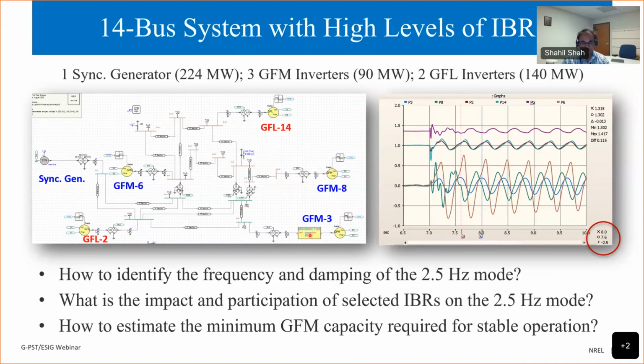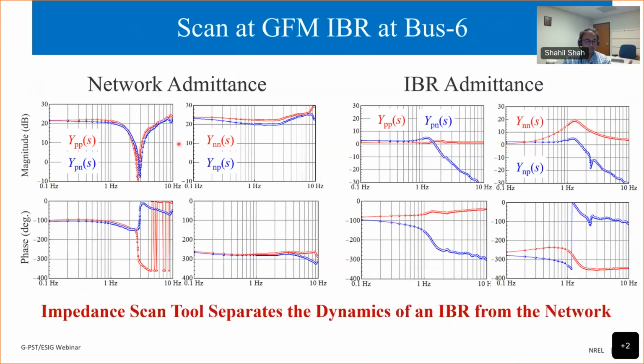Although here I am showing the block at the grid forming inverter at bus 3, first I'll show the impedance scans performed at the grid forming inverter at bus 6. Once we do that scan at this grid forming inverter at bus 6, this is what we get when we apply this tool. We see the network that this grid forming plant at bus 6 is seeing, the impedance of the network. And we also measure the impedance of that plant itself, or admittance, which are basically correlated.